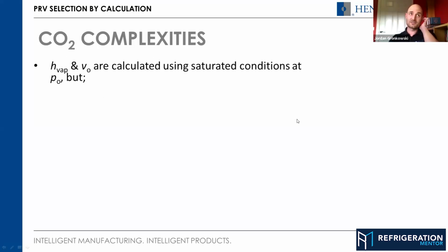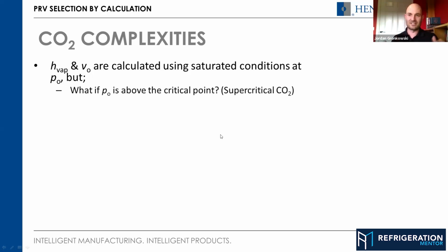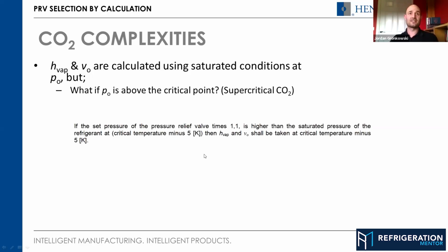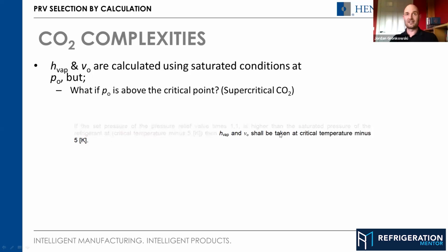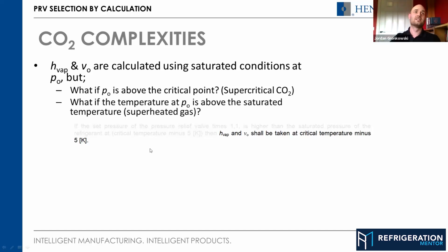So some complexities specifically for CO2. Eagle-eyed amongst you will have noticed that h_vap and ν0 are calculated at saturated conditions at P0. But with transcritical CO2, we're not at saturated conditions, we're above the critical point. So what if P0 is above the critical point, which is your supercritical CO2? This is what the standard says, but to paraphrase, if you're above the critical point, h_vap and V0 shall be taken at the critical temperature minus 5K. So when you look at your refrigerant properties, you go down 5K from your critical temperature, and that's where you take these values from, regardless of how high the pressure is.